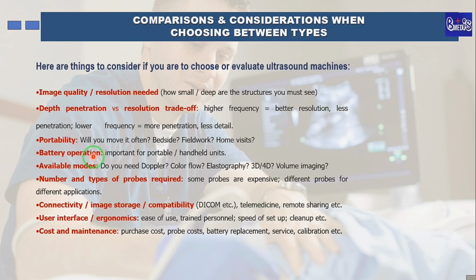Then battery operations, important for portable and handheld units. Then available modes. Do you need Doppler modes, color flow, elastography, 3D, 4D, volume imaging? If you need these, then you may have to go for the trolley-based ultrasound machine that gives all of these features. Then number and types of probe required. Some probes are expensive, with different probes for different applications. For instance, if you buy an ultrasound machine of 7 million that comes with 2 probes, to get an extra probe costs as much as 1 million. So when you are buying a machine, you need to take into consideration the number of probes to get, because those probes are very, very expensive.